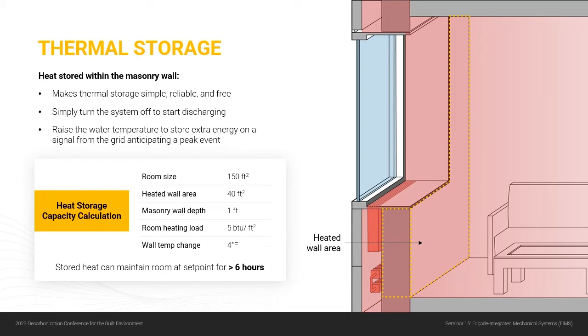And then what happens when we do this is we create this interesting effect where we're heating that masonry wall. So what we're doing is we're storing heat in that masonry wall. The masonry has a significant amount of thermal mass. So this is essentially free thermal storage. It's also extremely simple and reliable because basically all you have to do is turn the system off, or if the system is lost due to a power outage or something like that, and automatically that wall will just continue to radiate heat into the space. You can even do some interesting things, like if you're anticipating a peak grid event, you could raise your water temperature to push more heat into the wall in advance of that peak event. So there's some interesting things you could do with controls.